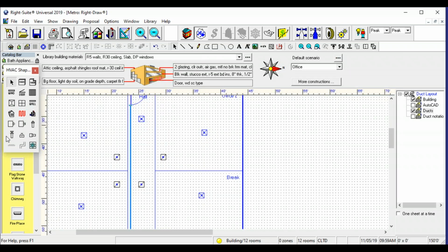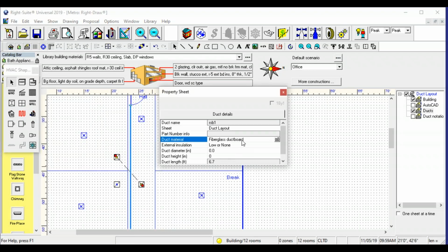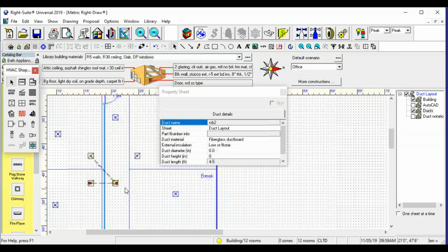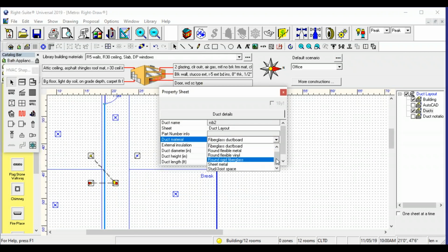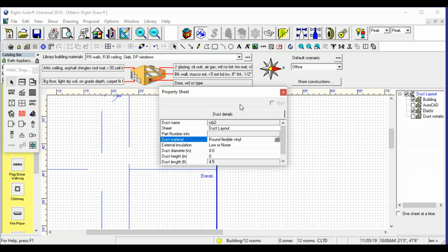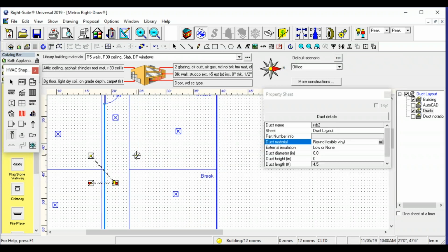All right, so now what these will do is these are going to be like a 24-inch tall cap. Sometimes it can be 16-inch tall cap. Made out of fiberglass duct board. They extend up, and then they're going to have a collar coming out the side to another tall cap over here. And then that helps with sound attenuation, and when you size it correctly according to Florida Building Code, with the volume of the diameter being 1.5 times the size of this incoming supply, then it makes it very, very efficient and a good mover of air out of that room. Now, the best way is always having that remote return, but you're not always going to get that. Sometimes you got to work with what you're given. And in this particular situation, this is what we're given.